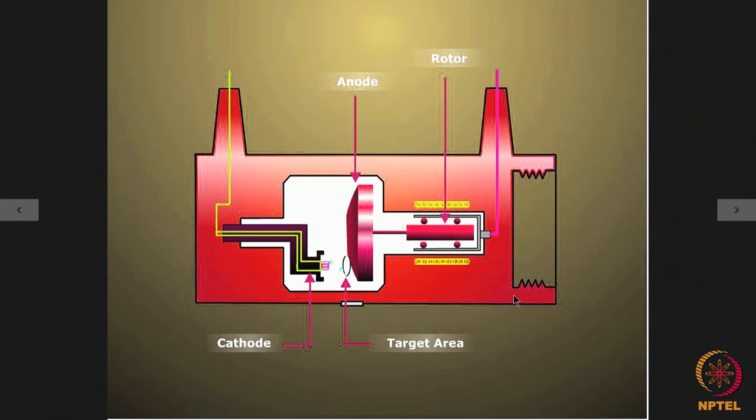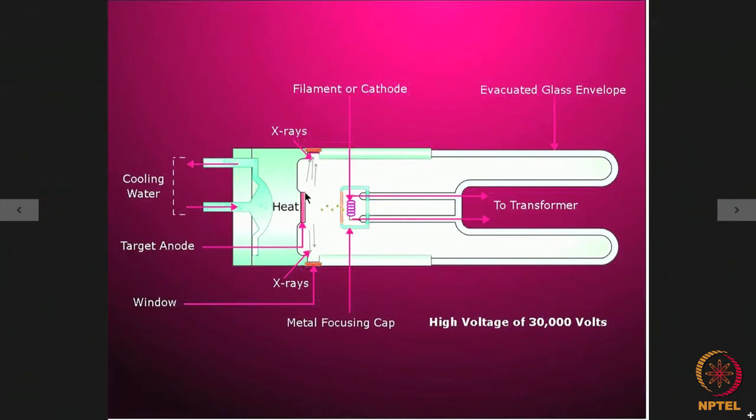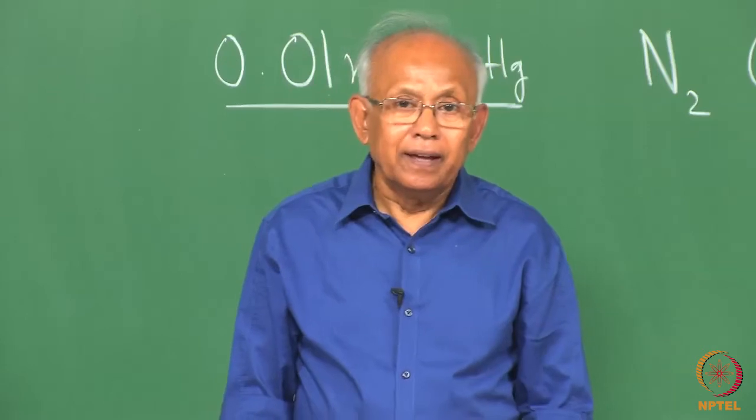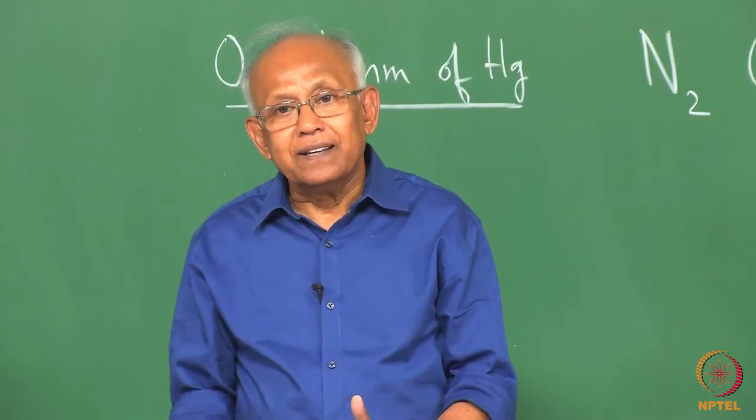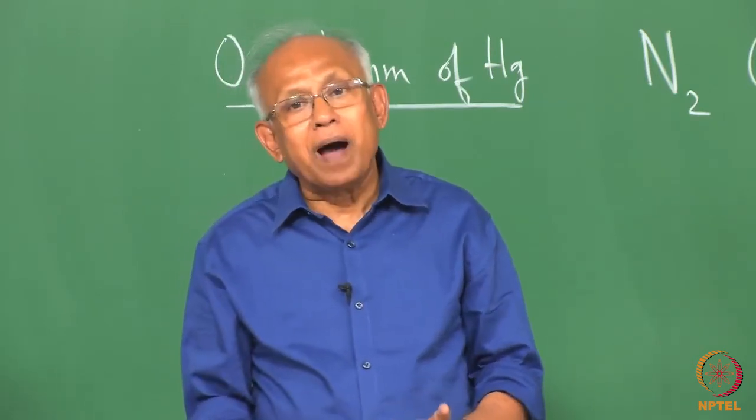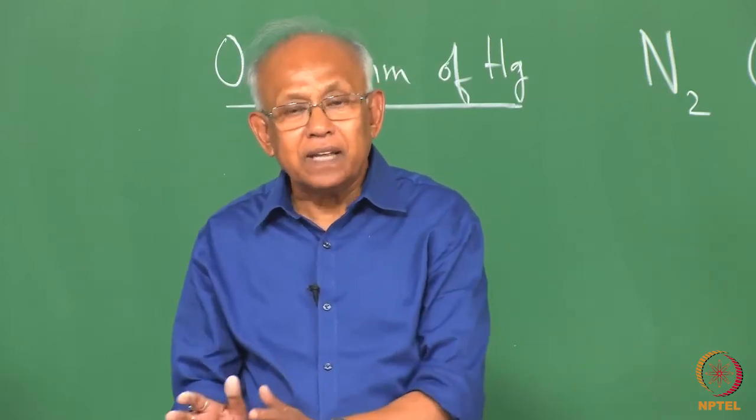There can be another type of x-ray tube also. In the previous case, the target is fixed here, the entire tube is sealed in the factory and it comes to the laboratory as such. If I want to have the provision to have a copper target, a molybdenum target and a chromium target, then I will have to buy three such tubes, one with a copper, another with a chromium, another with a molybdenum target.